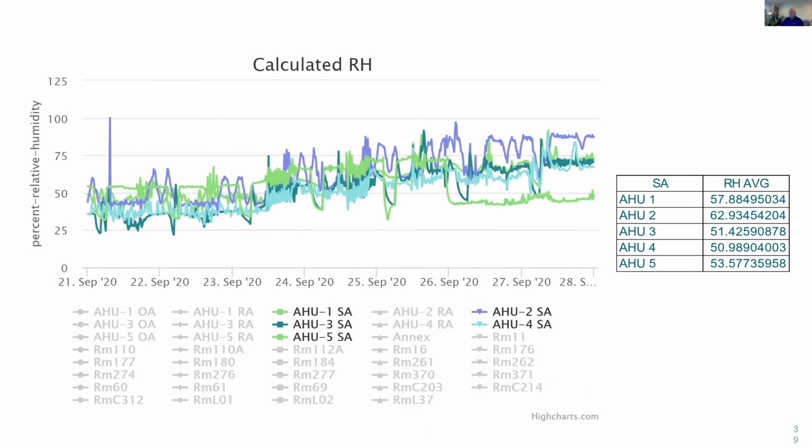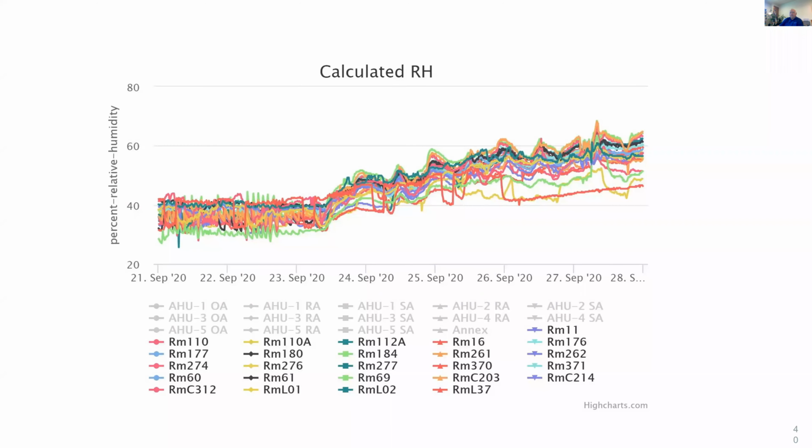Here's RH, relative humidity in the rooms, which has become very important. There's been a lot of studies now, or one particular, Dr. Taylor's done a lot of studies and published a lot of things about maintaining your relative humidity between 40 and 60. So these are the rooms now in this particular case, and you see they go down pretty low. They go down to 30 because it used to kind of be 30 to 60, but now they've tried to raise it some. Interestingly, I don't know if this is a weekend without looking back here that it's lower and it increases up here, but here's a trend that sees the humidity going up, in this case, above 60%. But like I said, when you see these types of things, this gives the whole building, and then you can hone in on something particular that you might want to look at a little bit more.